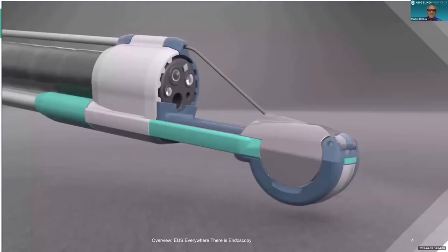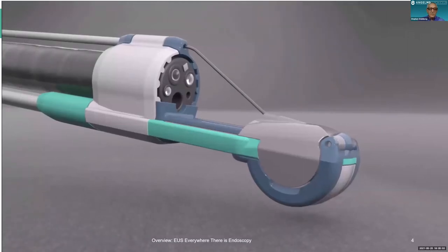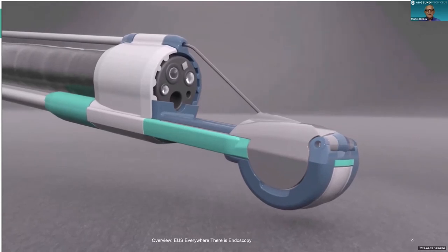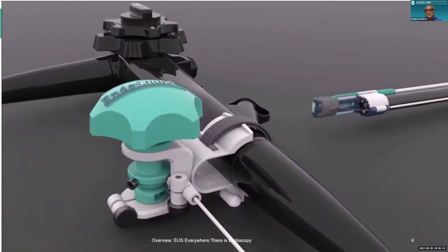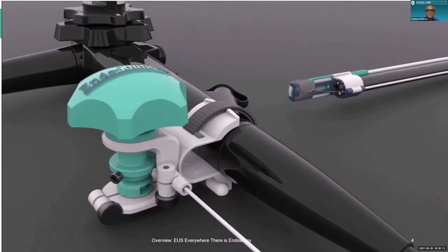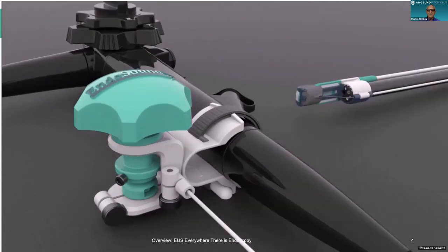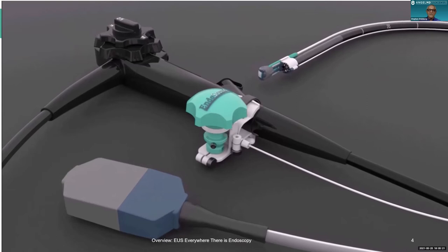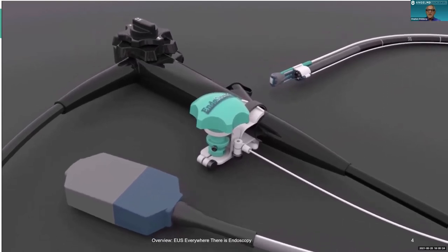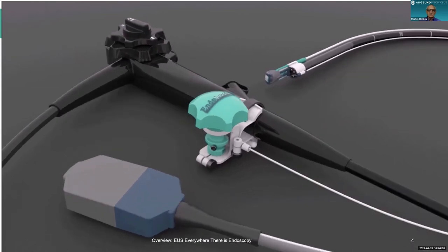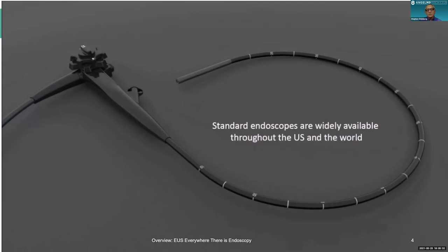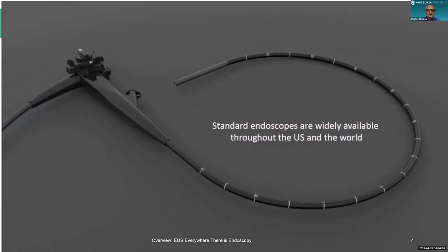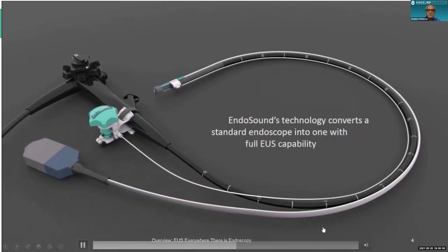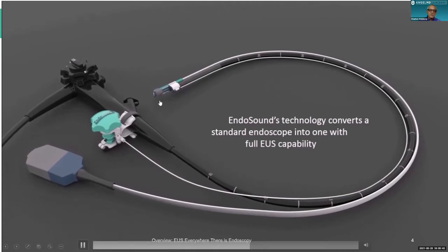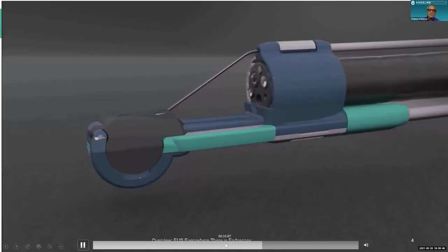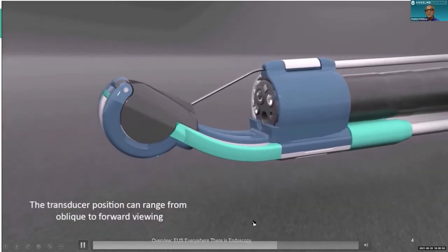So what's our solution? We developed a technology that allowed us to add this device to a standard upper endoscope, converting it to a fully functional EUS scope. And in doing so, we can do all of the procedures and more that our standard scopes can do. This conversion can be done in something under 5 minutes and takes this standard scope, found everywhere in endoscopy units, and converts it into a fully functional scope, with the transducer mounted here and control wheel here, allowing us to move the transducer and obtain different images.